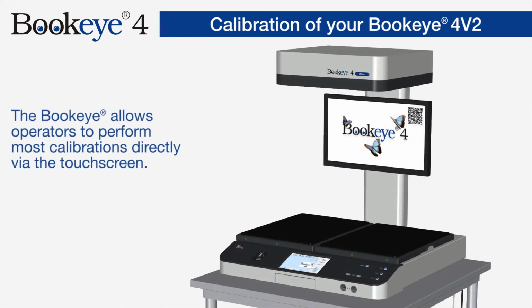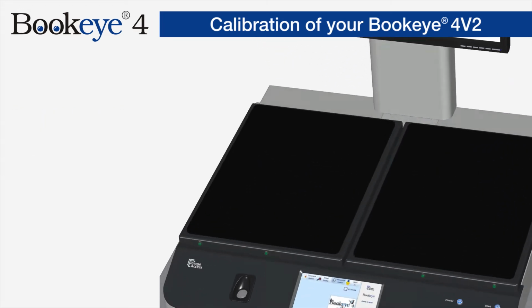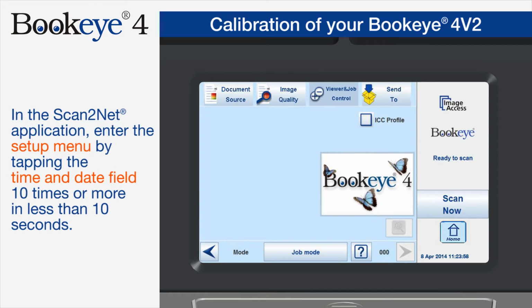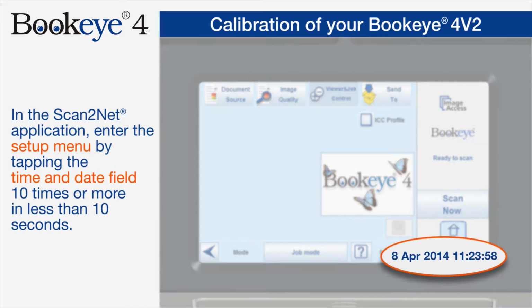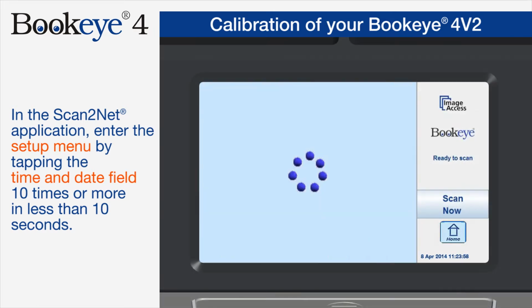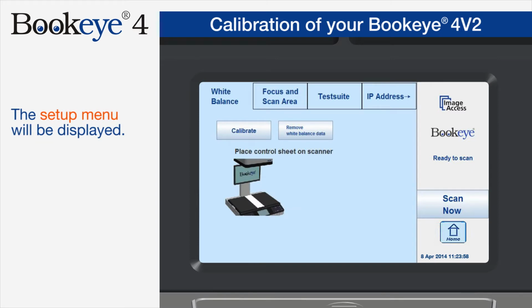The Bookeye allows operators to make most calibrations directly via the touchscreen. In the Scan2Net application, enter the Setup menu by tapping the time and date field in the lower right corner fast, 10 times or more in less than 10 seconds. The Setup menu will be displayed.